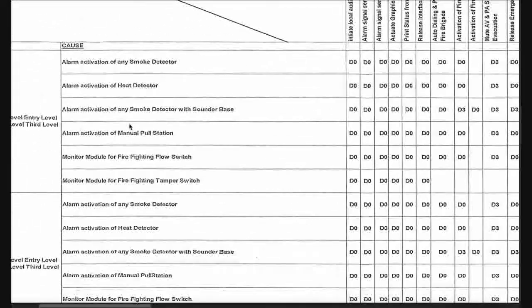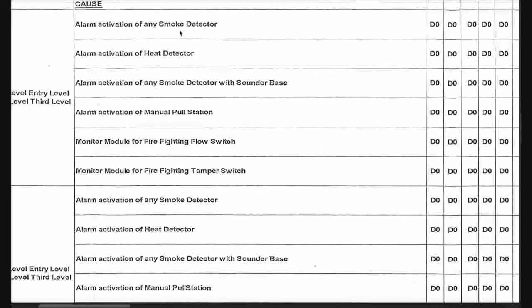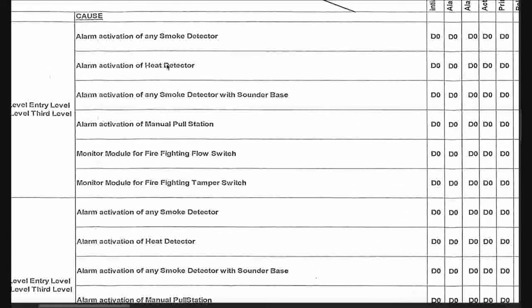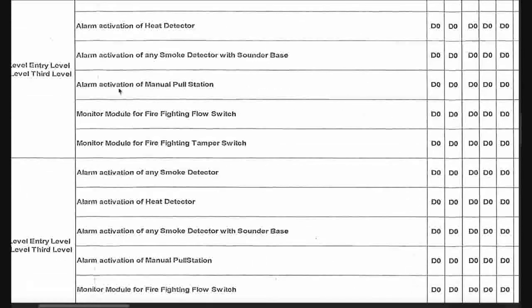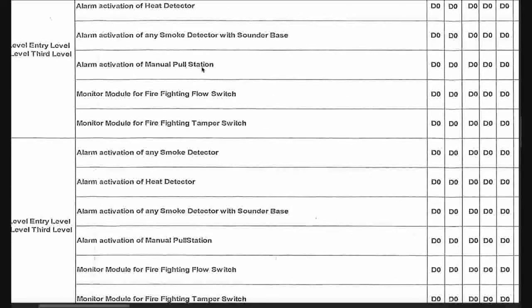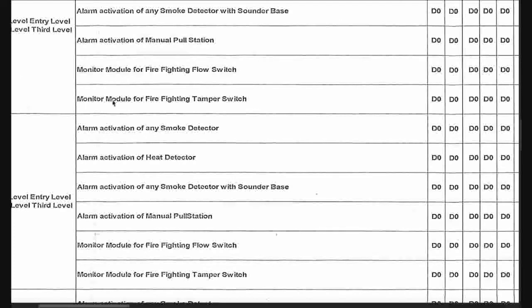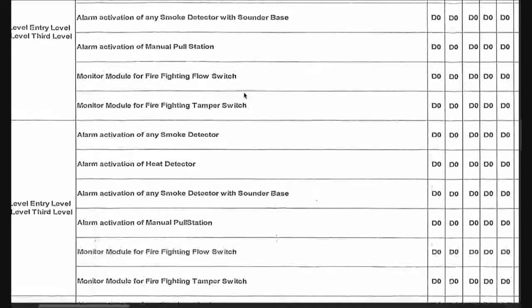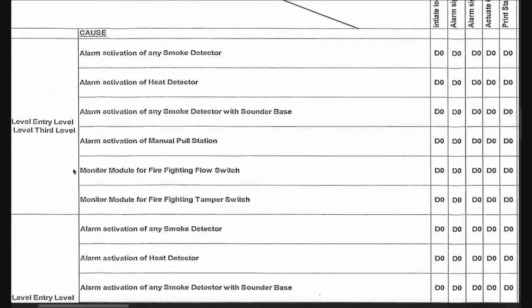Here we have the causes: alarm activated by smoke detector, or alarm activated by heat detector, or activation by both smoke detector with sounder base installed in a bedroom, or activated by a manual pull station on the corridors and stairs, or by a monitor module for firefighting flow switch — meaning the hose cabinet is used — or someone trying to open or close a butterfly valve.